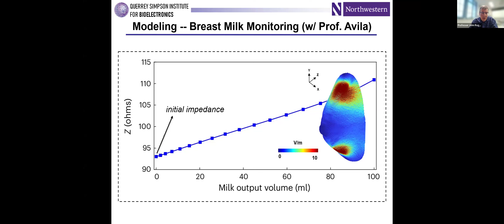And so the measurement technique really demands a fairly high level of accuracy. You need to really be able to measure a change in impedance to an accuracy of about 1% if you want to be able to make a useful measurement of this type to allow mothers to watch milk consumption in real time. So it required a fair amount of optimization around the electronics and minimizing the impedance between the electrodes and the surface of the skin of the breast. But if you're careful with a lot of those engineering factors, you can develop devices that offer the required level of accuracy in impedance measurement for this particular application.